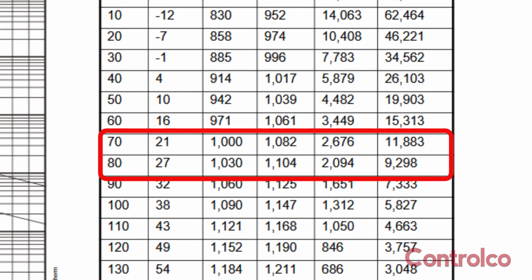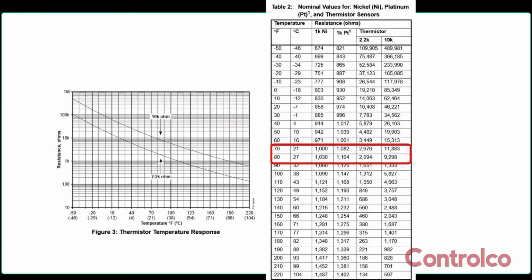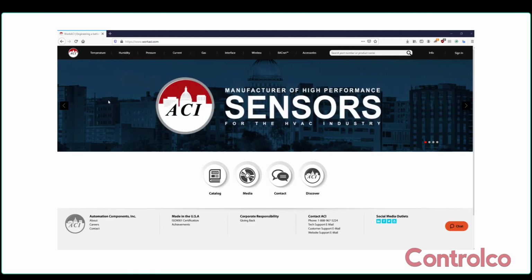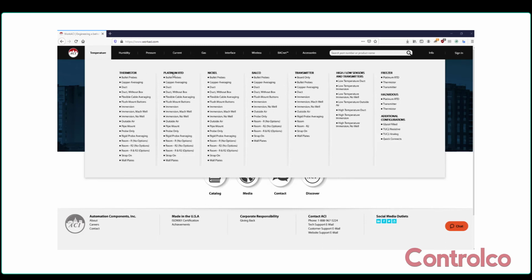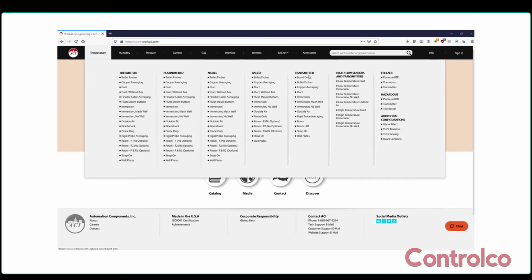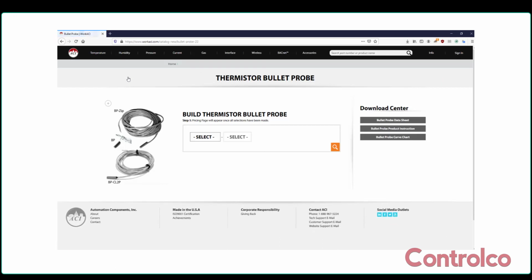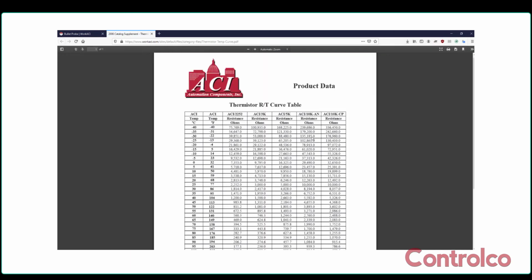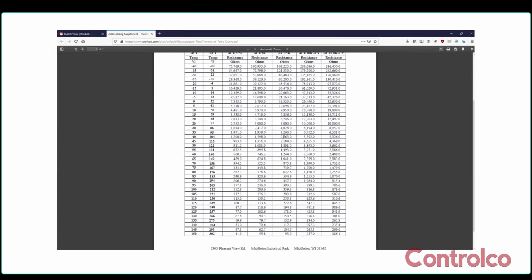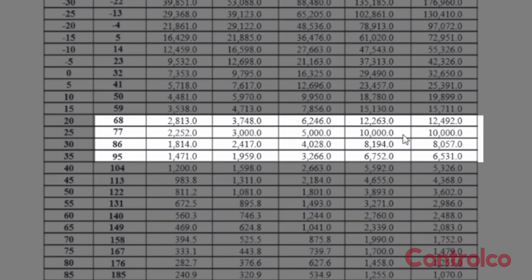So I found this really cool website. It's ACI Sensors. If you navigate to their site, this isn't a product plug or anything. It just happens to be very convenient. You can go to the temperature and you can grab one of their probes. And because this Johnson Controls sensor is a standard, this 10,000 ohm NTC is a standard, that means that any of the 10,000 ohm type 2 sensors will have the same scale. So if I look on my chart here, I can see that at 77 degrees, I should be at 10,000 ohms. That means that my room is warmer than that.